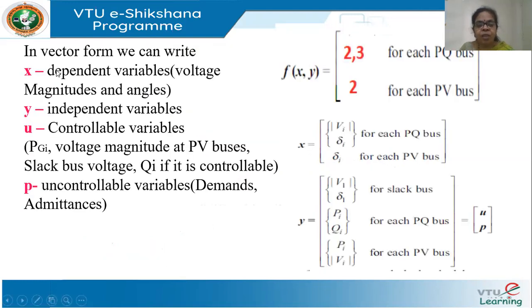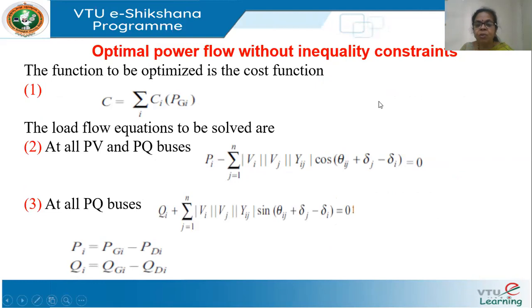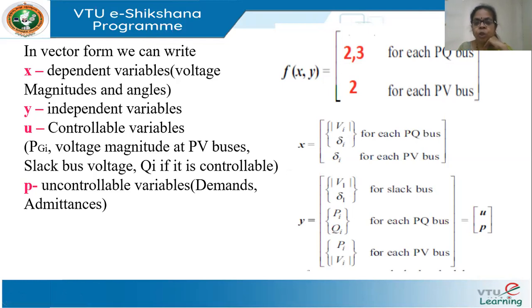In vector form, we write this as f(x, y) = 0, as used in Newton-Raphson method. So the set of equations — equation 2 for active power PI at PQ and PV buses, and equation 3 for QI at PQ buses only. For every PV bus, we only have equation 2 for PI, because QI is not specified there.